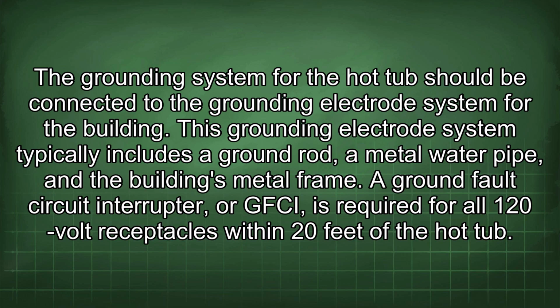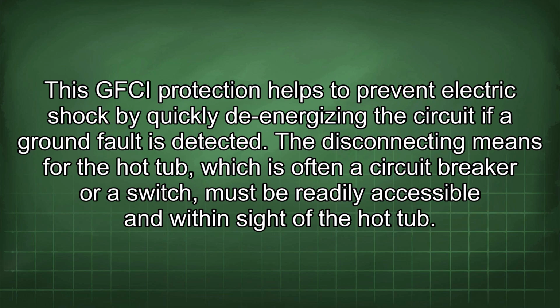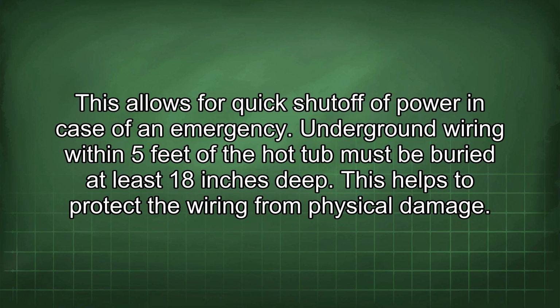A ground fault circuit interrupter, or GFCI, is required for all 120-volt receptacles within 20 feet of the hot tub. This GFCI protection helps to prevent electric shock by quickly de-energizing the circuit if a ground fault is detected. The disconnecting means for the hot tub, which is often a circuit breaker or a switch, must be readily accessible and within sight of the hot tub. This allows for quick shutoff of power in case of an emergency.